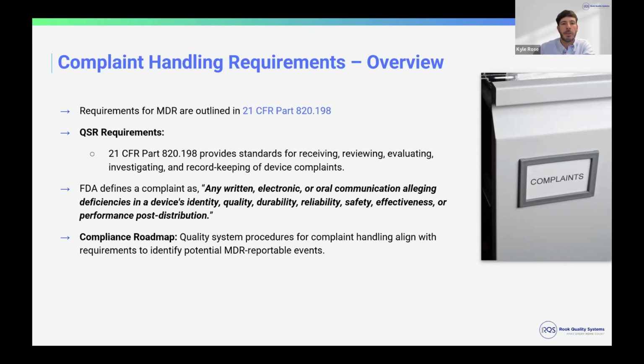Not all feedback that you get from people using your device or interpreting the results is necessarily going to be a complaint, but you need to have a process in place with procedures that outline what you define as a complaint and not a complaint, and then what steps need to be done once you've identified it as a complaint. One of the key aspects within the scope of FDA and complaint handling is the investigation of the complaint to identify what the issue is and what you need to do.